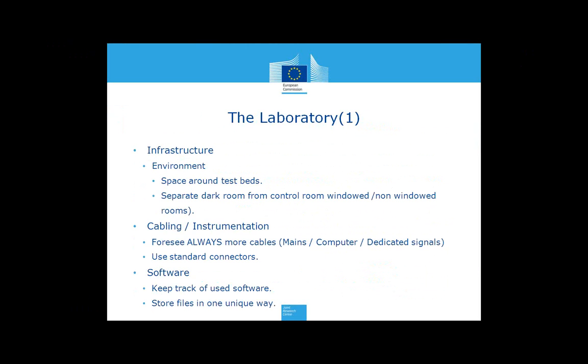Cabling and instrumentation. Always foresee more cables: mains, computer lines, telephone lines. Foresee more, because by the time you are finished, or by the time you think you only want to measure one module, your setup requires the measurement of one module with another reference cell, and so it's easier to have more cables already in place than pulling them in later. And the use of standardized connectors, whichever standardized connectors you take, is a plus, because it makes it easier to change between modules, between test beds, and between reference instruments.